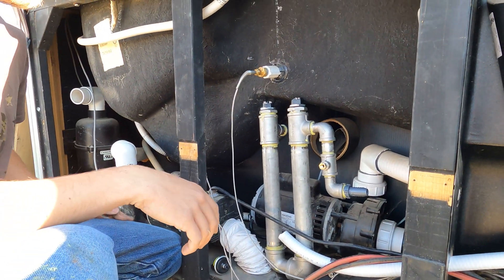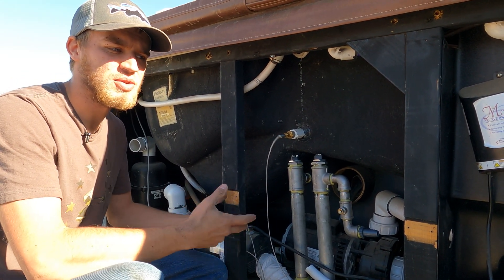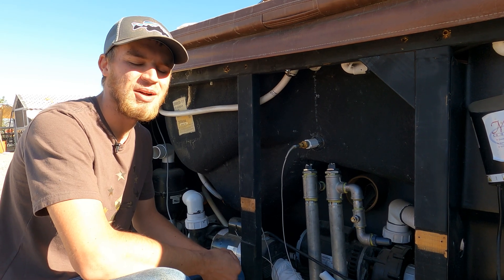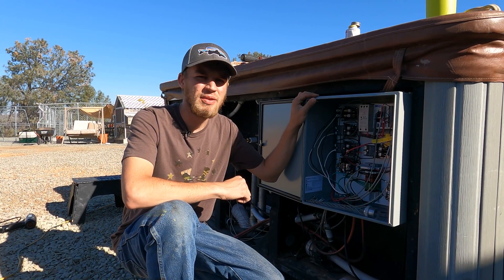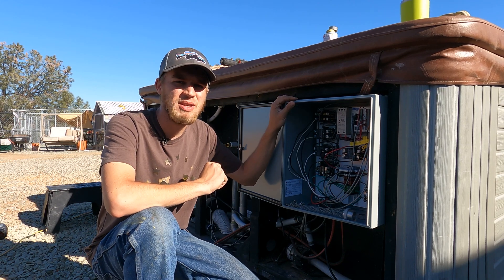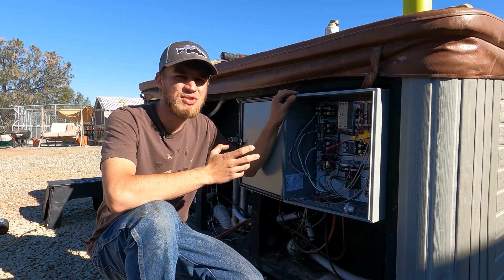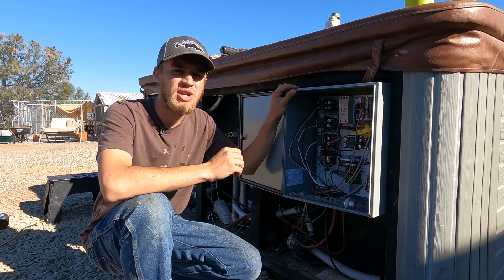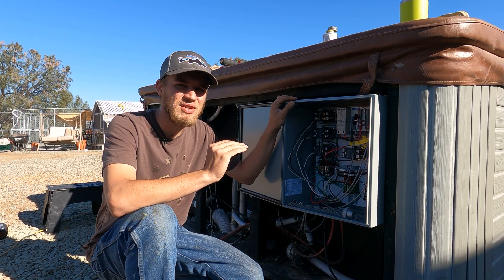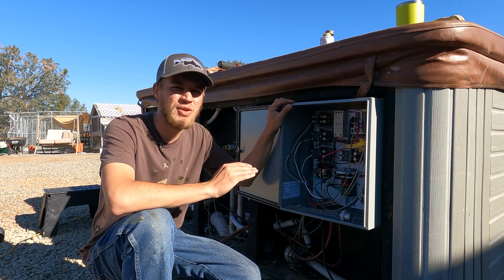I'm sure some of you guys kind of cringe when you see that but at the end of the day this whole spa is connected onto GFI breakers. So the concern of having a short or ground fault and causing electrocution of the people in the spa is pretty minimal because of that GFI protection. One of the other things we take advantage of to heat this spa effectively is when the generator is running we run these heating elements at full blast. The Sol-Ark that we just installed has a generator peak shaving feature, so we can program that we want 13,000 watts of load on that generator and if anything else turns on it'll taper back charging or even go into inverting mode to make sure we never overload the generator.